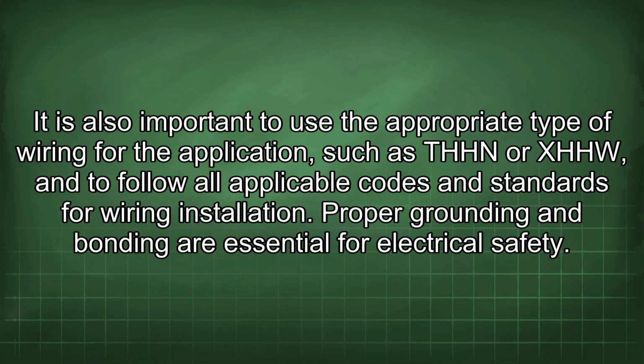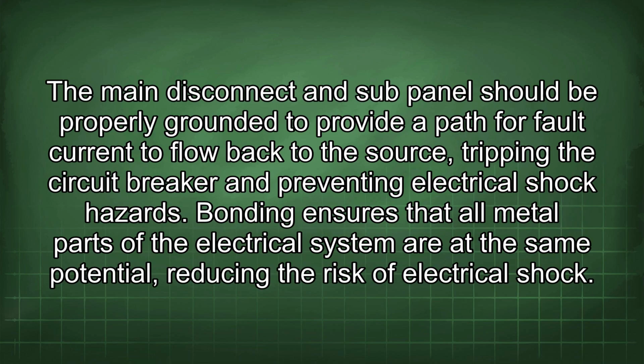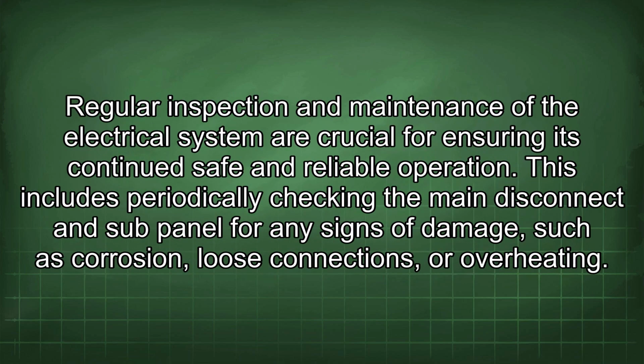Proper grounding and bonding are essential for electrical safety. The main disconnect and sub-panel should be properly grounded to provide a path for fault current to flow back to the source, tripping the circuit breaker and preventing electrical shock hazards. Bonding ensures that all metal parts of the electrical system are at the same potential, reducing the risk of electrical shock. Regular inspection and maintenance of the electrical system are crucial for ensuring its continued safe and reliable operation.